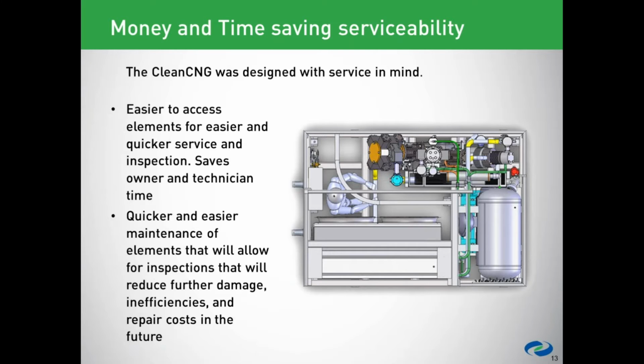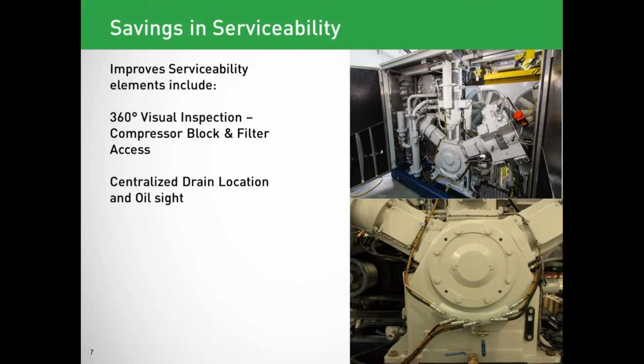So a couple of specifics on the serviceability. The first one, as I mentioned earlier, is 360-degree visual inspection of the compressor block and filter access. As you can see in the top right-hand photo, opening the front air intake louvers provides complete access to the front of the compressor block. And then walking inside the service access provides access to the rear side of the compressor block. This allows the compressor block to be serviced much easier and also allows for inspection and preventative maintenance as required.